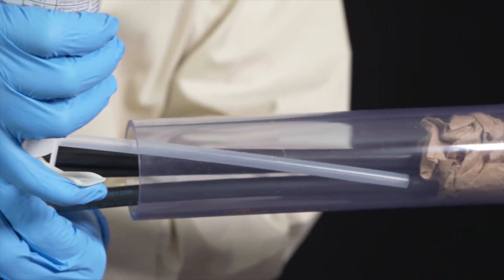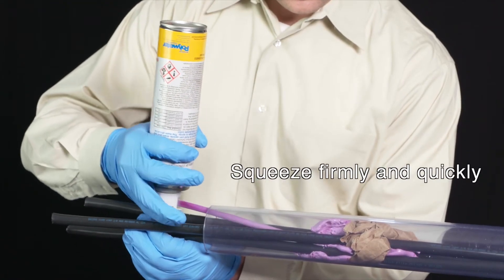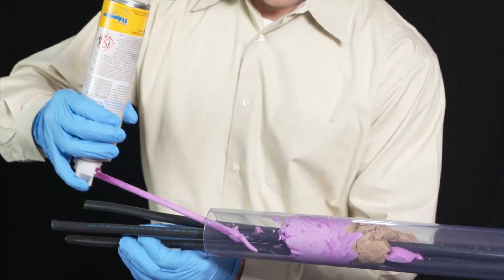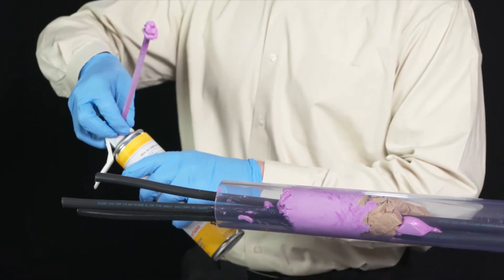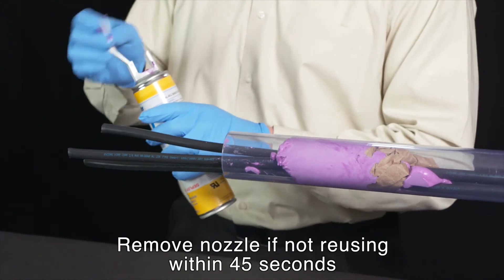Insert the nozzle all the way into the seal space. Squeeze the trigger firmly and quickly, making sure that it's fully depressed. When filling conduits, move the actuator nozzle to all areas of the conduit to ensure a complete seal. Make sure to spray between cables.